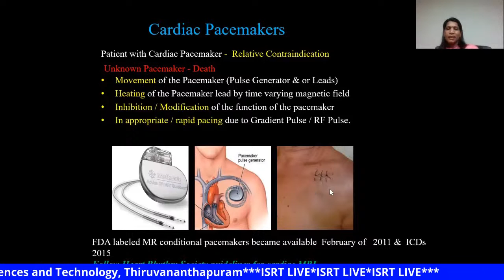Cardiac pacemakers are considered contraindicated in an MR environment because these pacemakers are active devices. The static magnetic field can cause movement, heating, or inhibition of the function of the pacemaker, or inappropriate or rapid pacing can occur due to the gradient or the RF pulse. So a patient with a cardiac pacemaker is considered contraindicated. It was an absolute contraindication earlier. Now, from 2011 onwards MR conditional pacemakers, and from 2015 onwards MR conditional ICDs, are available. Now we have data about patients who have undergone MRI with conditional and non-conditional devices. Now the cardiac pacemaker is a relative contraindication.